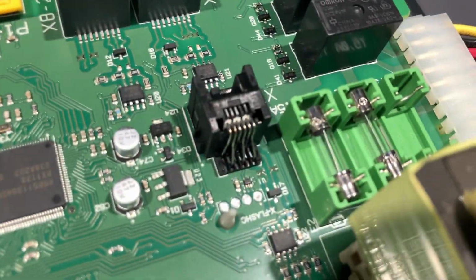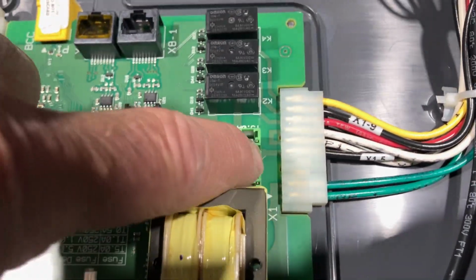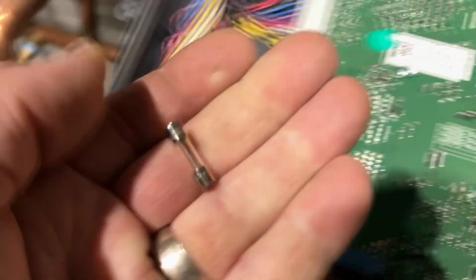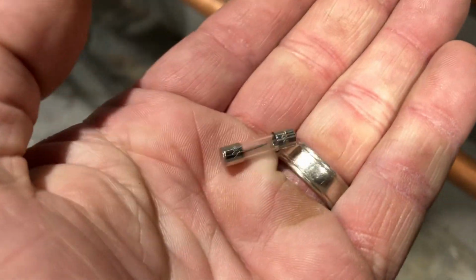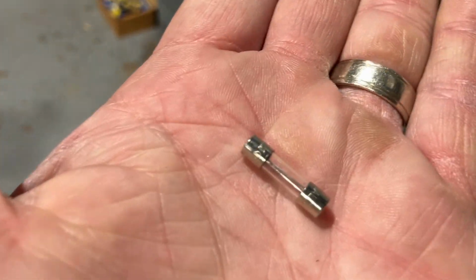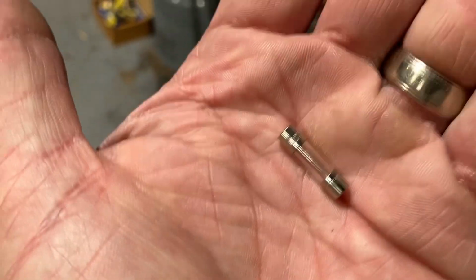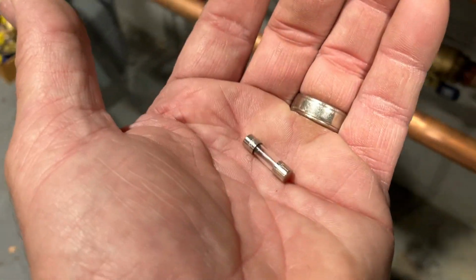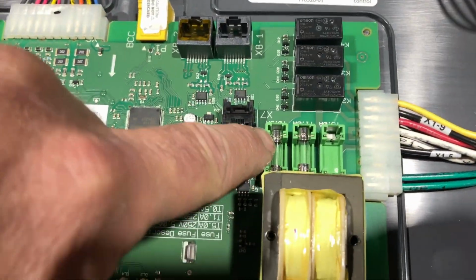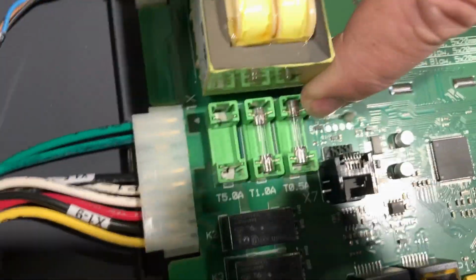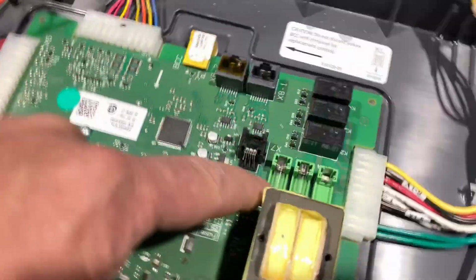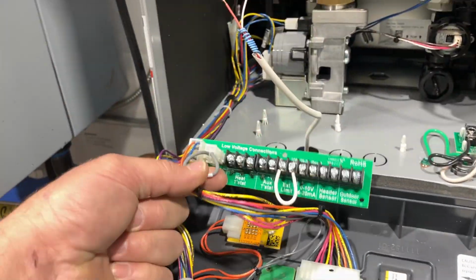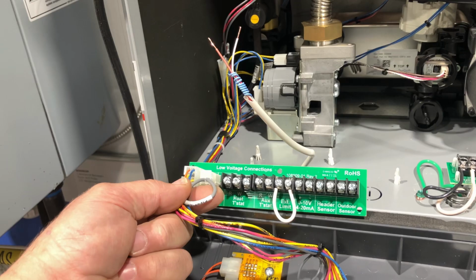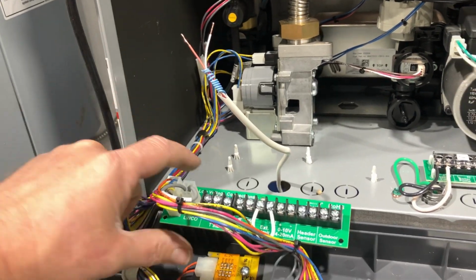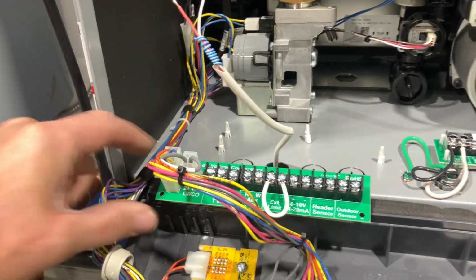All right, we took a close look at all the fuses now. I took the one from the right and put it to the one on the left. There is the fuse. We tested continuity on it. There is no continuity on it. If you take a close look at it, it is burnt out. Now this fuse holder, that one, is power going to our low voltage connections, printed circuit terminal block there.